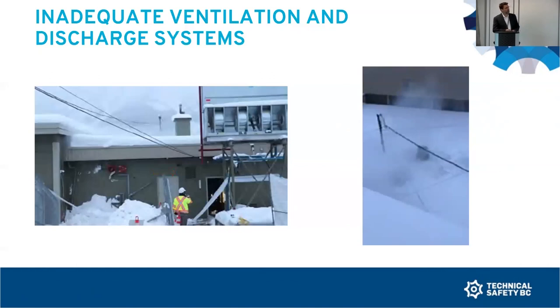event. The other thing that we noticed was that there were two fans here, a large fan that was installed for leak rupture scenarios, as well as a small fan here. And the small fan was evacuating all of the smoke. But in this pocket, it just drifted over toward this inlet on the arena side. So we could see evidence of it just drifting over and going toward an air inlet of some type on the arena side. So it's very important to understand the air movements when you're trying to evacuate something, so that you don't bring it right back into the building.